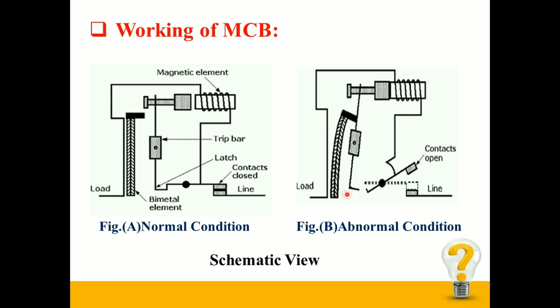During the short circuit condition, heavy current passes through the solenoid, which is also called the magnetic element, and this forces the plunger towards the latch. Due to this, the mechanical latch is released and the contacts are separated, which prevents damage to equipment from the heavy short circuit condition.